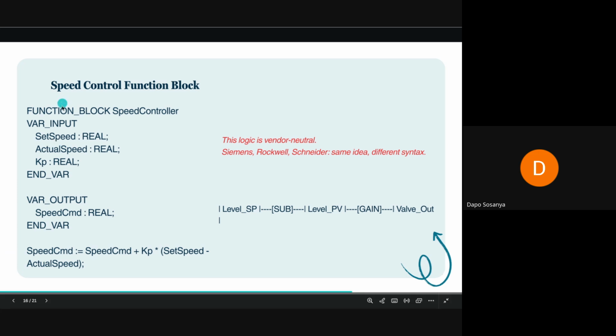So if you convert this into ladder logic with, let's say, 100 rungs, the controller starts from rung 0 on the left, scans it, gets the output, goes to rung 1, scans it, gets the output, goes to rung 2, and so on - as it scans, it updates all the internal registers with values, so that by the time it gets to rung 100 it goes back again. If level PV changes, it has already gone through and updated that register. But if it's on rung 50 and level PV suddenly changes, that won't have effect until it finishes this scan and goes back again.